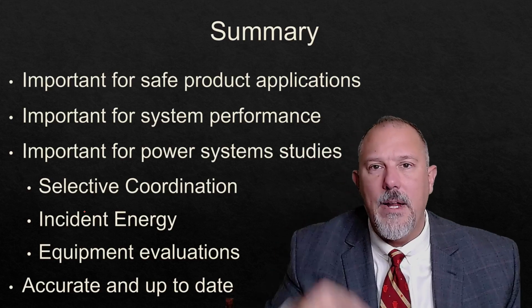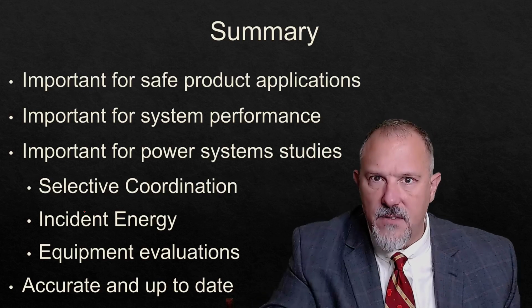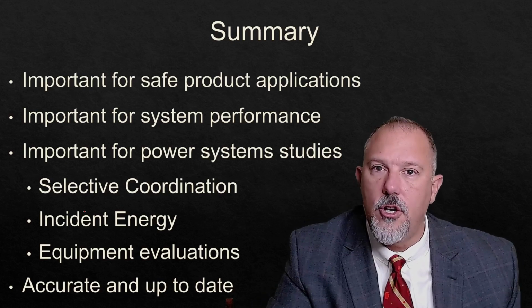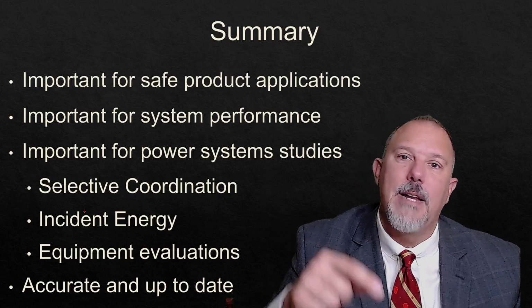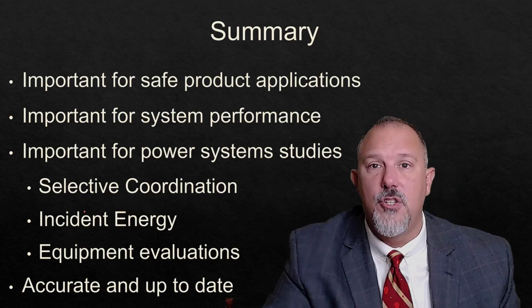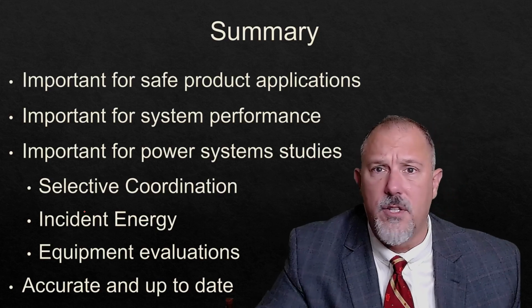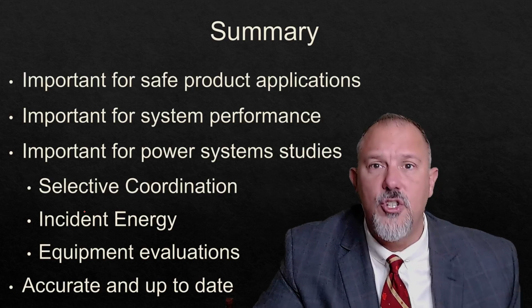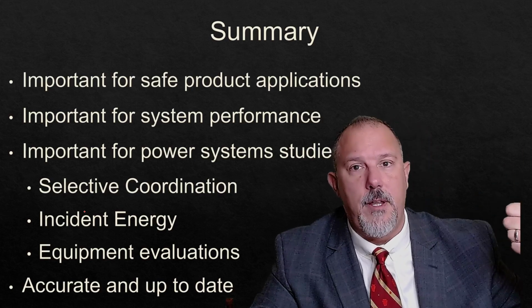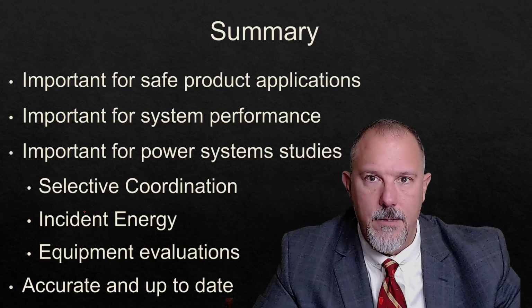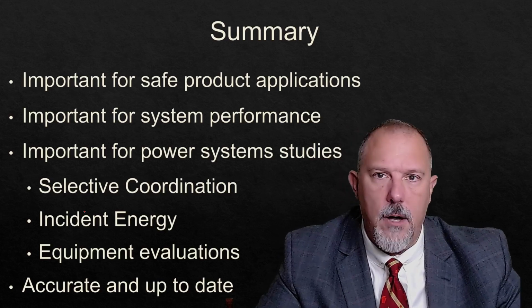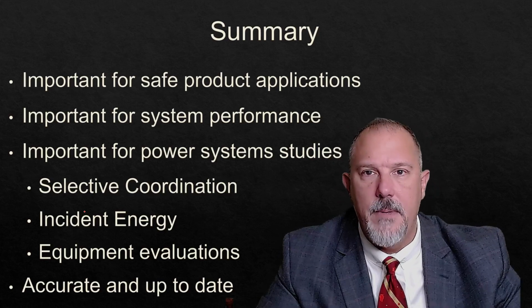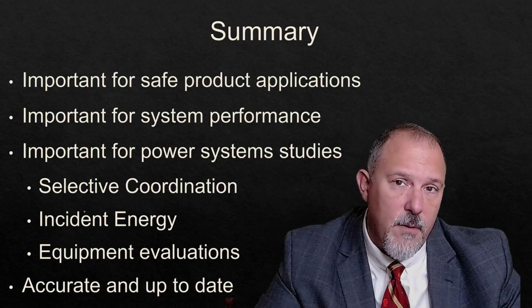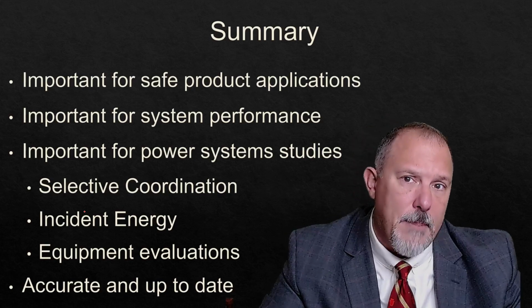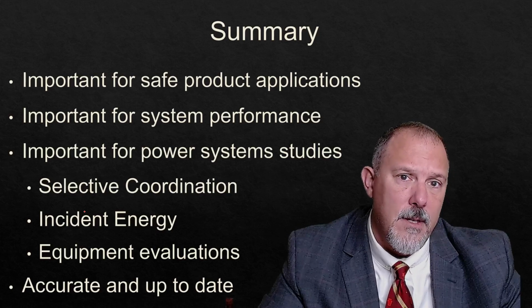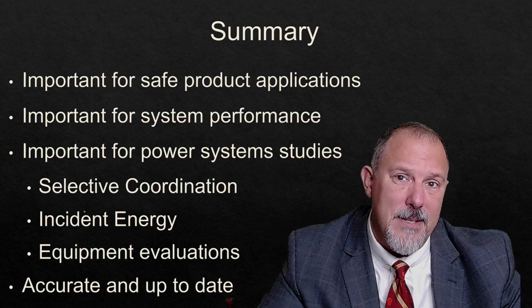At every point, everywhere where you apply a piece of equipment, you need to make sure the short circuit current rating is greater than the available fault current at that point in the power distribution system, regardless of where it's at in the power system. You don't just rely on one device upstream to knock down your current everywhere. Every piece of equipment, every component, every overcurrent device has to be evaluated against its available fault current at where it's applied in the power distribution system. Else you have an unintended rapid disassembly in the field.